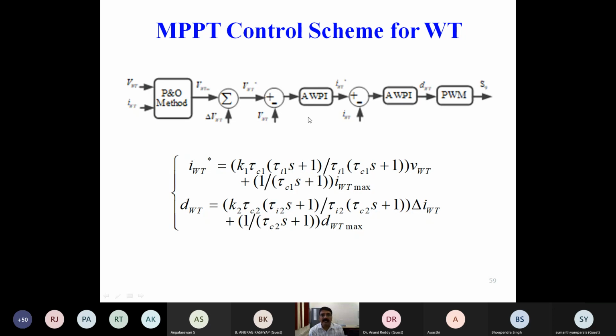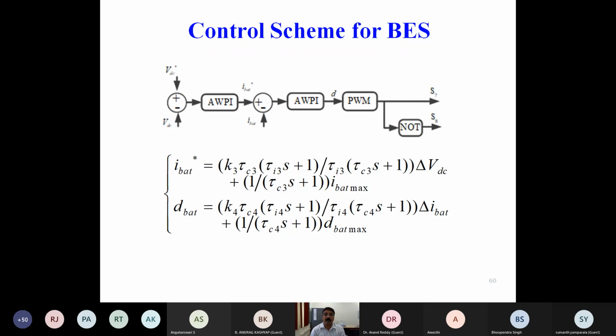Because in a proportional integral controller, there is a problem of saturation. If it operates with a longer error, it saturates and cannot change suddenly. Suppose your error is very high, then the PI controller will take a longer time to control the system if it is not tuned properly, or even if it is tuned for steady state conditions where the error is small. Now if there is a transient condition where the error is large, it will go into saturation. For that, we need an anti-wind-up algorithm, which reduces sample-to-sample saturation errors so the system becomes faster.